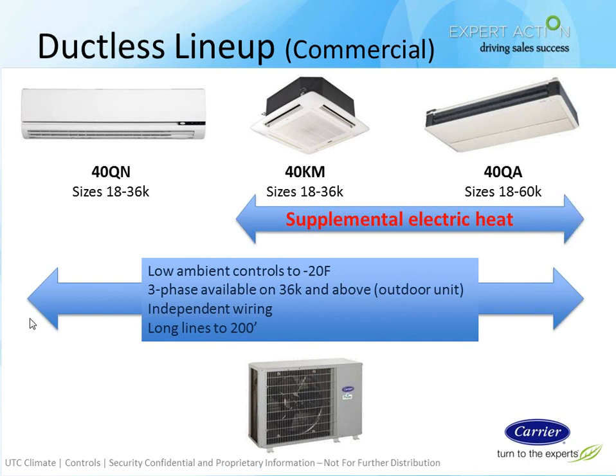On units 36,000 BTUs and above, 3 tons through 5 tons, those do come in 3-phase voltage. These must be independently wired. That is, the outdoor unit has to have its own separate power supply, as does the indoor unit. Again, for commercial applications where it's needed, we can do long line set runs up to 200 feet on some of these models. Check with TEC for support on that piping issue.